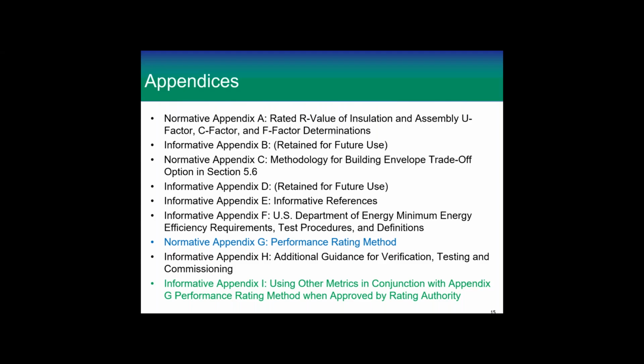So you're at the end of a project, you've spent millions of dollars, you're getting commissioned. We put a rule in about commissioning, and you fail. Well, what happens? Tear the building down or what? So we get a lot of arguments and a lot of stuff about commissioning. So we ended up with having some commissioning in the standard, and then this informative appendix that gives you a lot of guidance on commissioning.